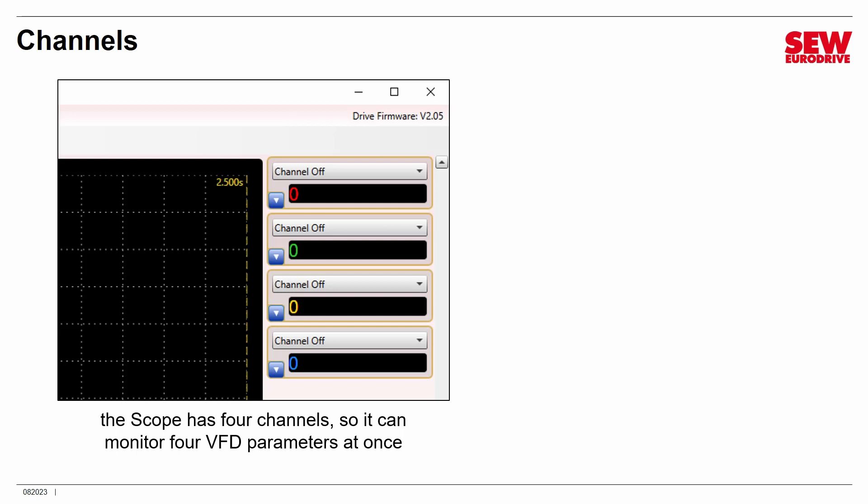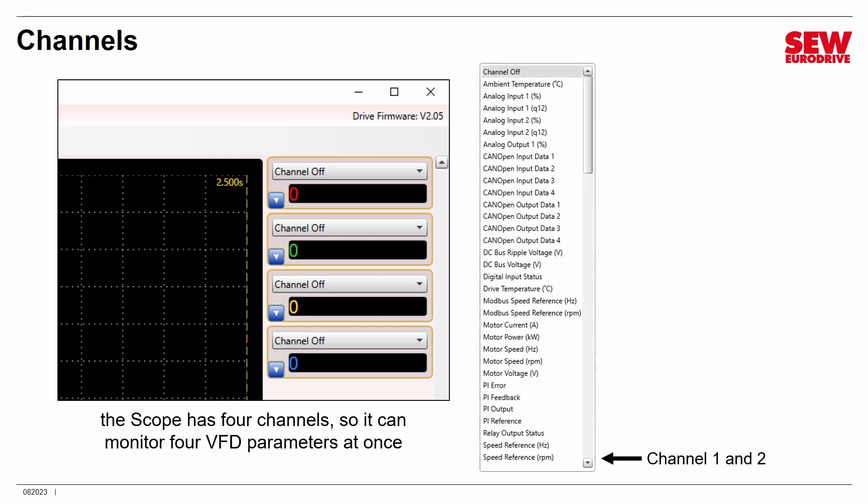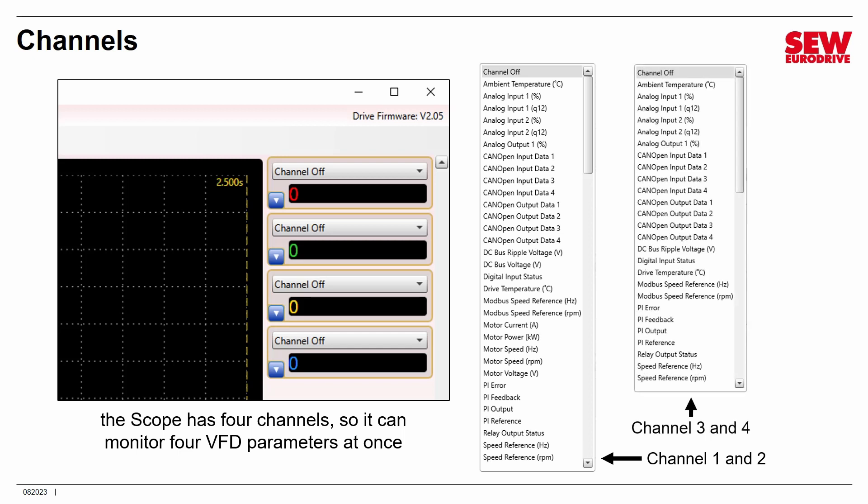Here's one thing that's very important to understand: channels one and two can monitor quite a few different parameters. You just click the little down arrow next to the channel and pick the parameter you wish to monitor. Channels one and two are pretty thorough, but channels three and four are a little more restrictive — there aren't quite as many parameters available. So you may have to do a little juggling in order to monitor the parameters you're interested in. For example, motor current, motor speed, and DC bus voltage are only available on channels one and two, meaning you can't monitor all three at the same time. Do look at these lists and pick your channels and parameters carefully.